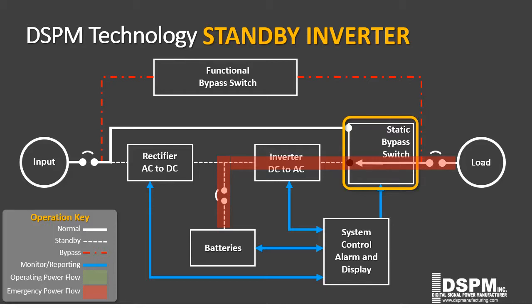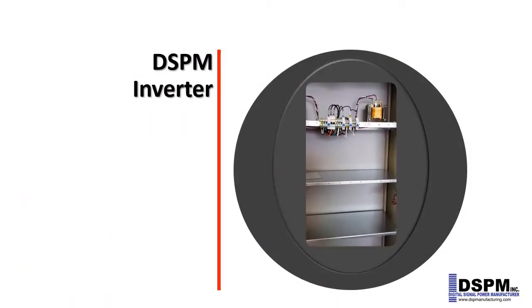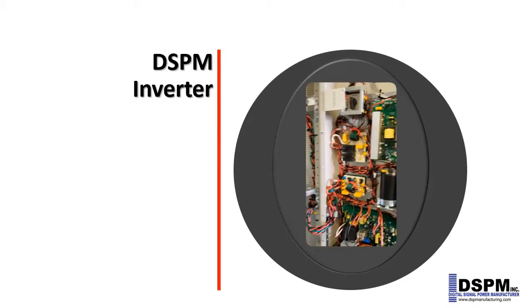In the event of a power failure, illustrated by the red line, the static bypass switch quickly and seamlessly transfers to the standby batteries in 16 milliseconds or faster when needed. The good news is, systems such as lighting will never notice the transfer time. However, high-speed digital equipment may be sensitive to the short switching delays and as such may not be a candidate for DSPM standby inverters.